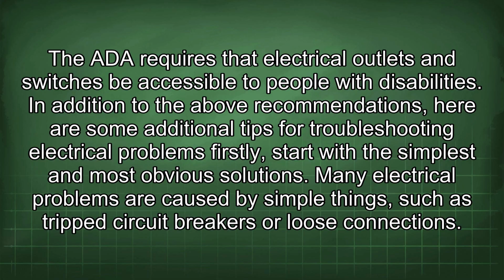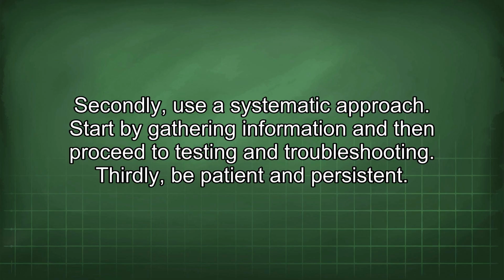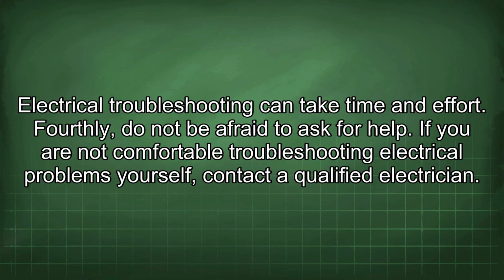In addition to the above recommendations, here are some additional tips for troubleshooting electrical problems. Firstly, start with the simplest and most obvious solutions. Many electrical problems are caused by simple things such as tripped circuit breakers or loose connections. Secondly, use a systematic approach. Start by gathering information and then proceed to testing and troubleshooting. Thirdly, be patient and persistent. Electrical troubleshooting can take time and effort. Fourthly, do not be afraid to ask for help. If you are not comfortable troubleshooting electrical problems yourself, contact a qualified electrician.